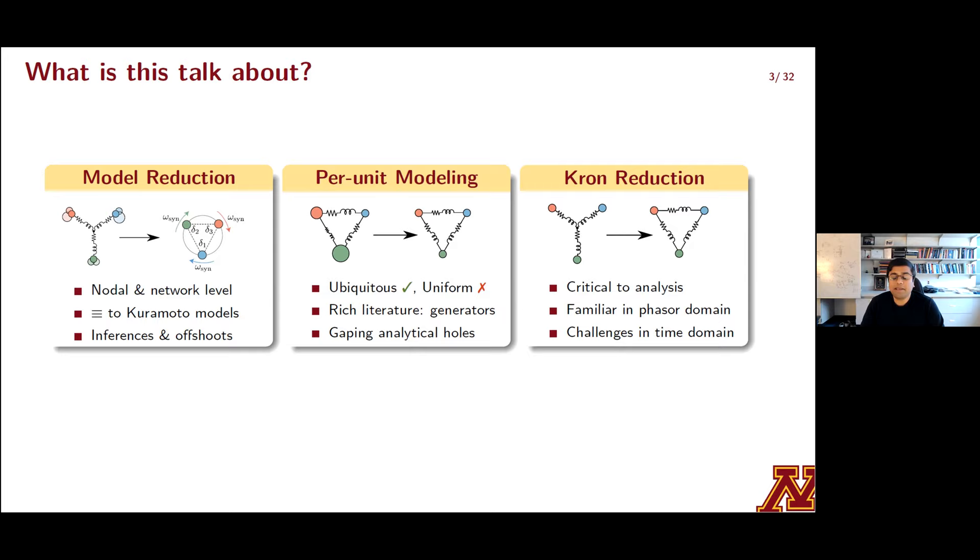While undertaking this modeling effort we encountered some key challenges and we bumped into a few open questions for two tasks that were pervasive in our effort. These two topics are per unit modeling and Kron reduction. We'll focus on these in the second and third portions of the talk but just a quick snapshot of what's lying ahead. Per unit modeling is as ubiquitous as it's not uniform. In my mind that's a dangerous combination. There's a rich literature on per unit models for synchronous generators but frankly several gaping holes when it comes to applying similar ideas for normalizing dynamics of power converters.